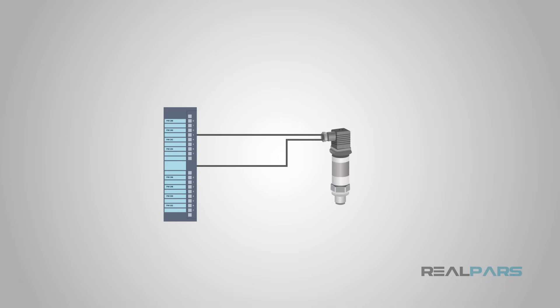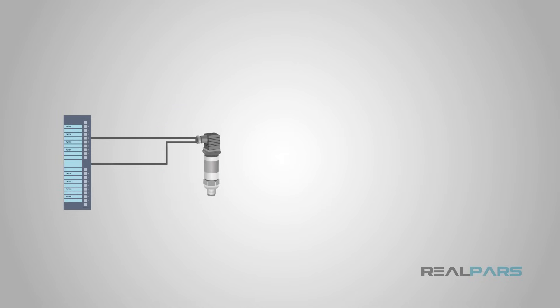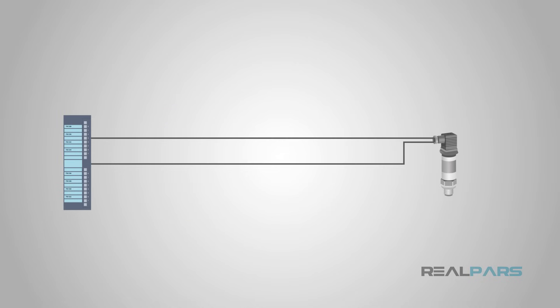Another positive feature of analog sensors and transmitters is that the signal can be carried a great distance along a single pair of wires with little or no signal loss. A current signal can be transmitted up to 1,000 meters through 18 gauge wires with no appreciable signal loss.